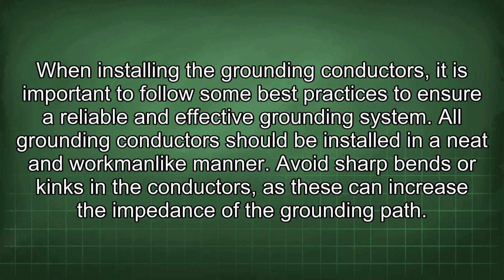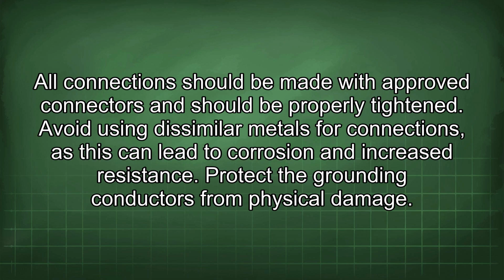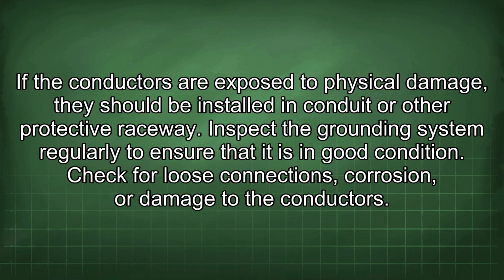When installing the grounding conductors, it is important to follow some best practices to ensure a reliable and effective grounding system. All grounding conductors should be installed in a neat and workmanlike manner. Avoid sharp bends or kinks in the conductors, as these can increase the impedance of the grounding path. All connections should be made with approved connectors and should be properly tightened. Avoid using dissimilar metals for connections, as this can lead to corrosion and increased resistance. Protect the grounding conductors from physical damage. If the conductors are exposed to physical damage, they should be installed in conduit or other protective raceway.